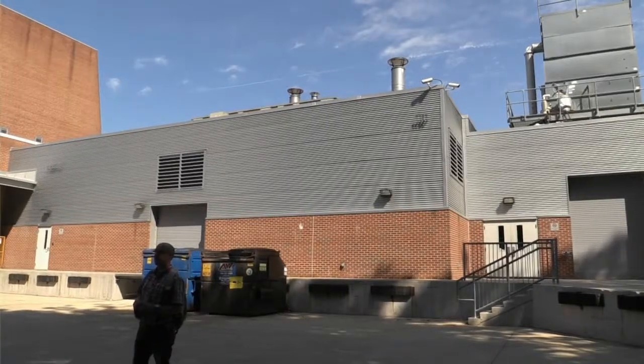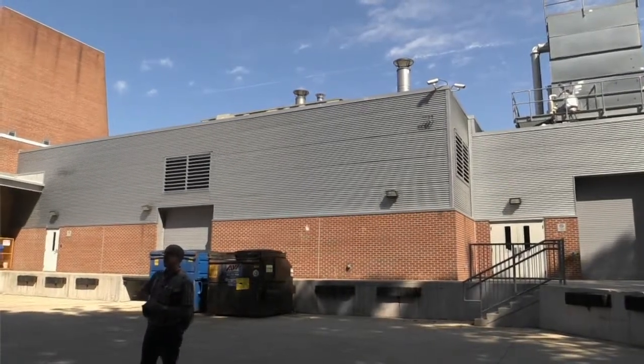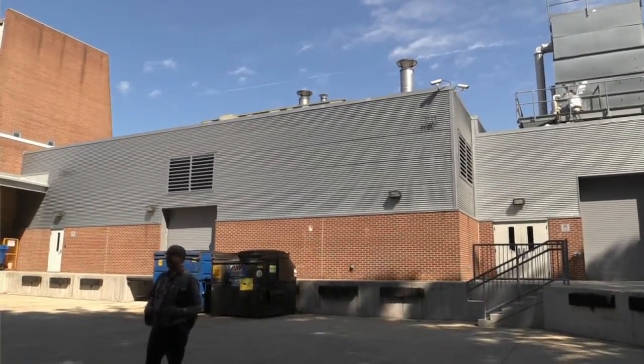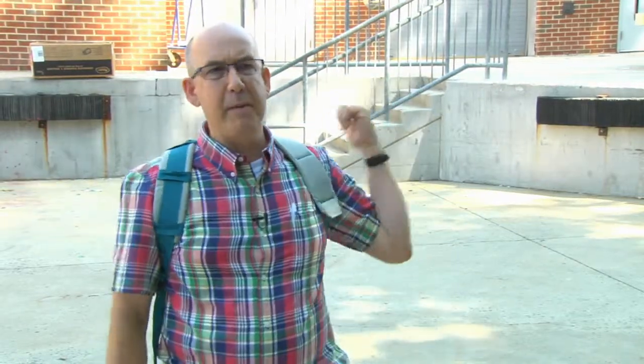We've got a chiller plant behind me. You can see the tower. You can see the stacks for the boiler. That tells me there's some heavy equipment behind me. If there's people bringing in equipment, doing maintenance, are they leaving the roll-up doors open? Is the space conditioned? If it's conditioned and I see the roll-up door open, that means I'm letting that conditioned air, whether it's wintertime or summertime, run right out of the building. So those are some of the things that we want to be aware of.